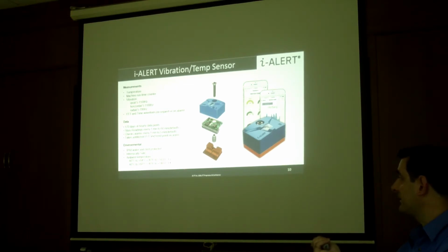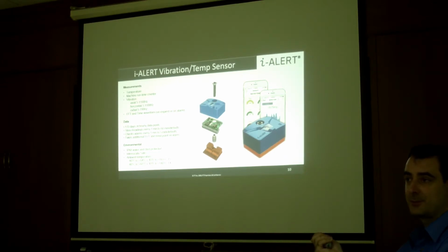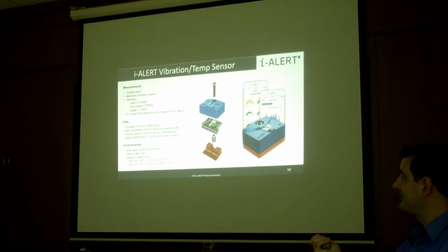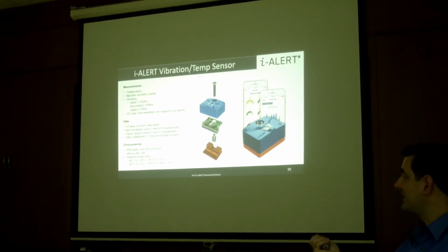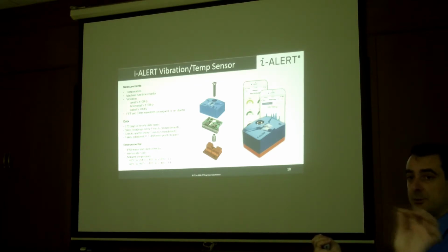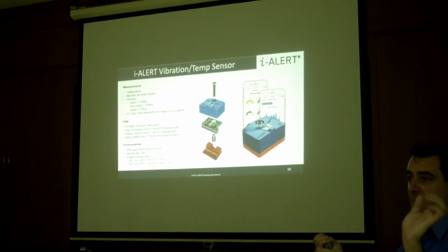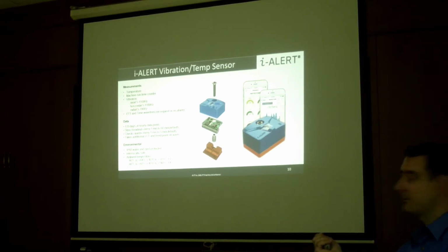So here is the latest specs. We can do a little bit extra frequency, which is very useful for low running speeds. And our default settings are 60 minutes for recording the data and 5 minutes for checking. You can now change that down to 1 minute, but your battery life will go right down. So this is 3 or 4 month life. If you make the sample time every minute, save a data point every minute, you will use the battery in 1 month. It's only 1 month. But sometimes customers like that for troubleshooting. Works for troubleshooting.